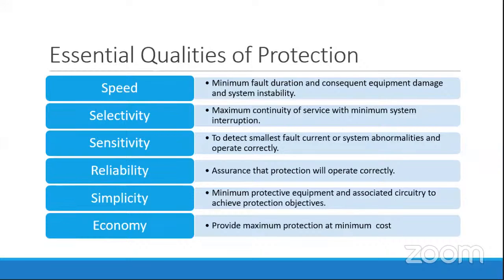Selectivity means maximum continuity of service with minimum system interruption. The switch gear we use for protection should be able to withstand the maximum amount of current which the equipment is rated for, such that in normal conditions the equipment would not operate or give a fault command to any other circuit breaker or switch gear. And simultaneously, it should also be able to interrupt the system in minimum time, at a minimum amount of fault current, so that the system can be saved from getting damaged.